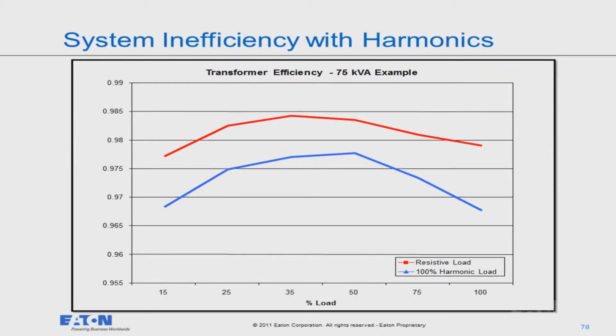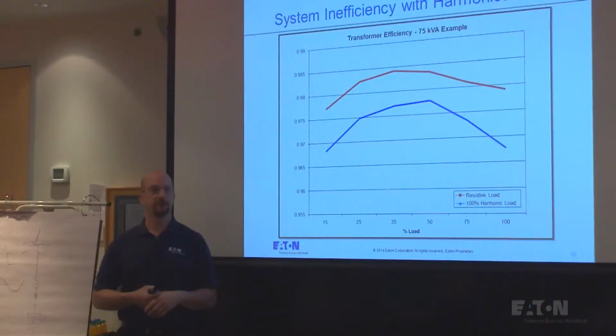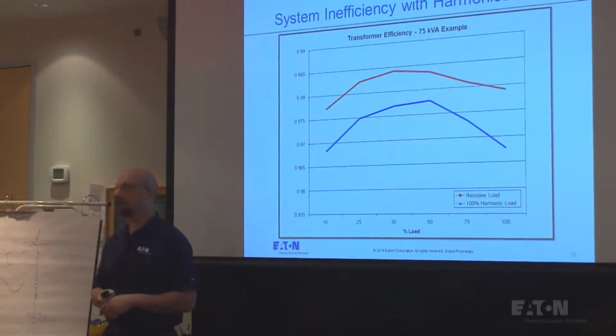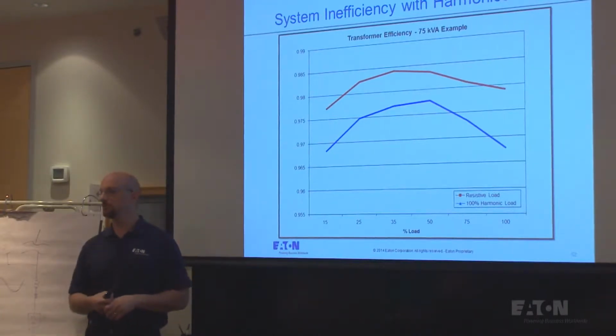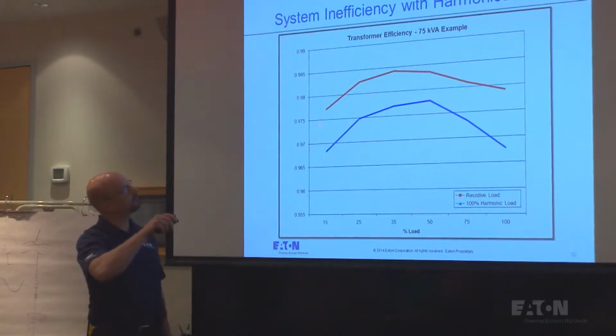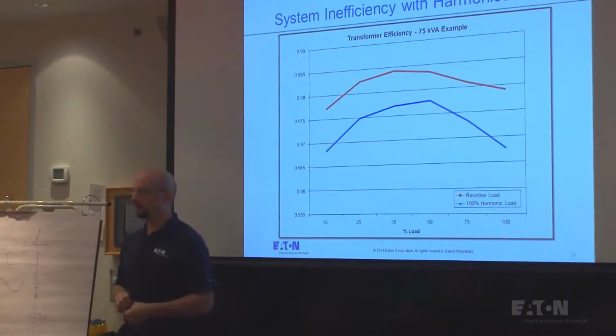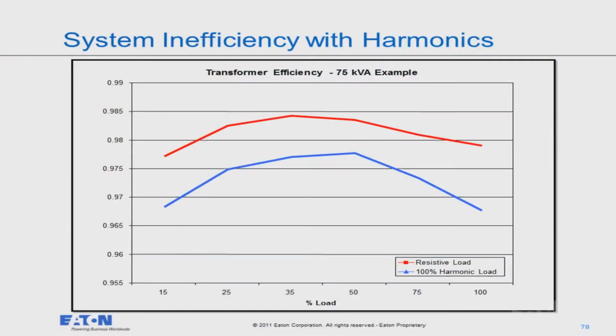So if somebody sells you a magic box that they say, put this in and it'll get rid of all your harmonics and you're going to save about 30% of your power, is that true? No. Now if they say it saves about 30% of your losses, is that true? Pretty close to true, right? Because your losses here were 2.5% and now they're like 1.5%. So people can play games with words, but the ultimate idea here is that you're only saving 1% of your losses, if you filter it out 100%.